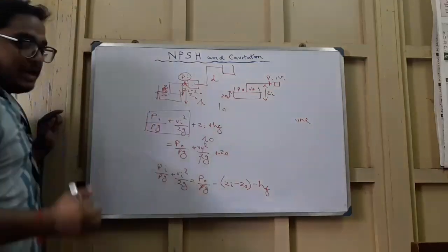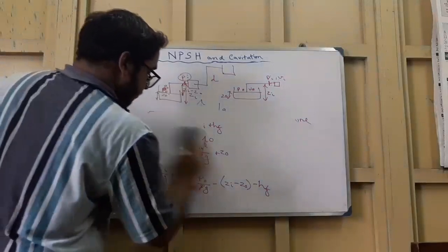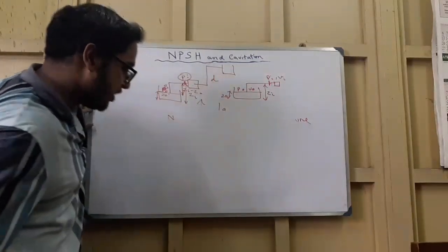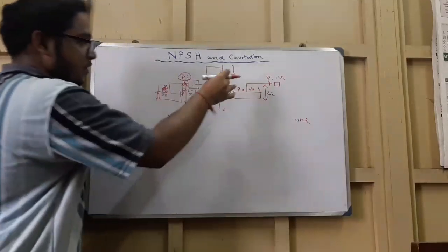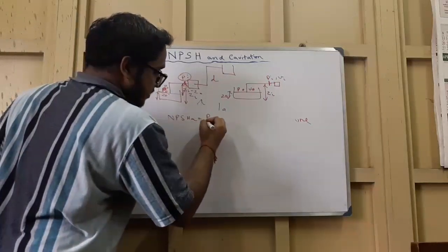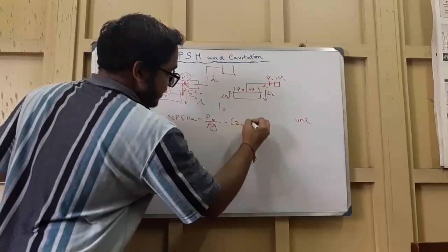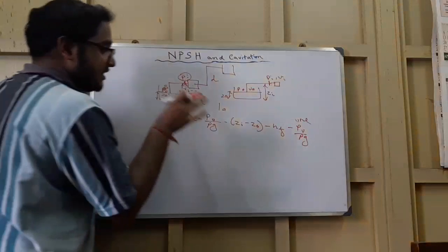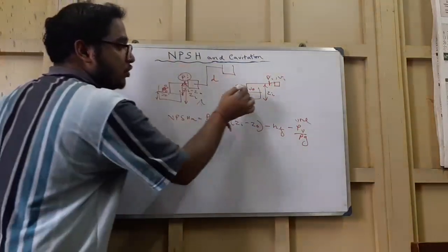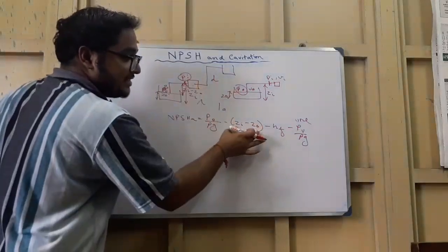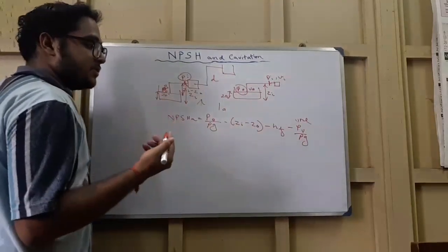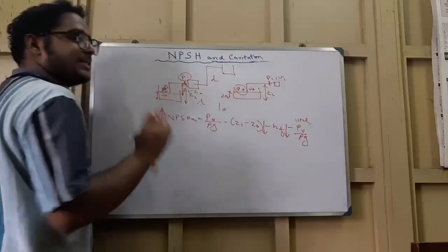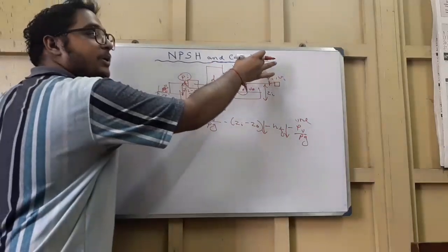Rearranging, we get: PI/ρg + VI²/2g = P0/ρg − (ZI − Z0) − HF. Substituting into the NPSH Available expression: NPSH_A = P0/ρg − (ZI − Z0) − HF − PV/ρg. We have now expressed NPSH in terms of reservoir pressure P0, the gravitational head difference (ZI − Z0), the frictional losses HF, and the vapor pressure PV/ρg. To keep NPSH high, these losses must be kept as low as possible.